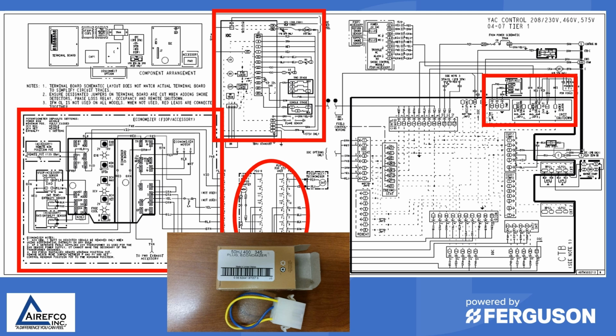So usually changing the main board does not get you anywhere unless the traces on the back of the main board become cracked or broken and lose connection. So next time you have a larger system like this where you have to troubleshoot an electrical issue, try the isolation process to try to find out where the problem is.